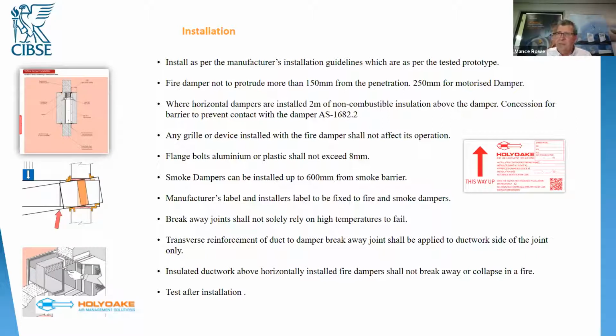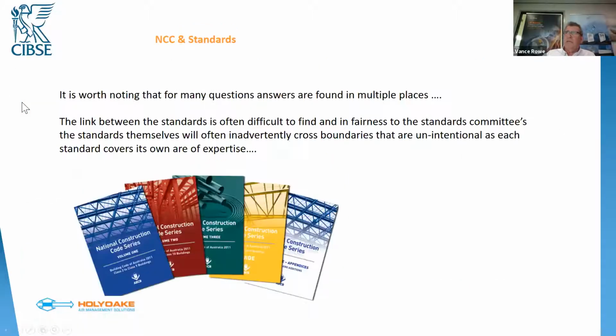For those of you who know me, this is almost a mantra for me: always test fire dampers after installation. I've had some very embarrassing times with fire dampers from time to time being racked in trucks and racked during installation. And it's not always easy to tell whether there's been damage to a fire damper or a fire damper sleeve before you install it.